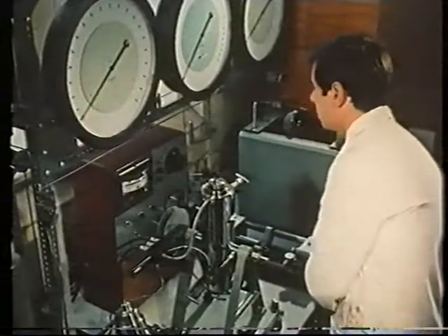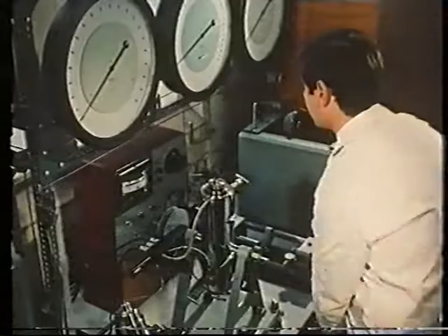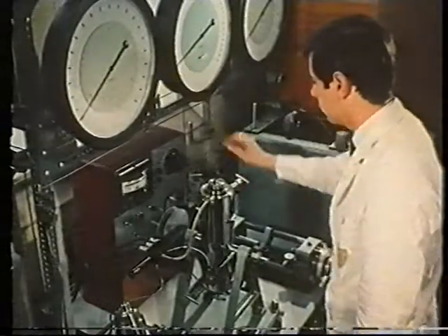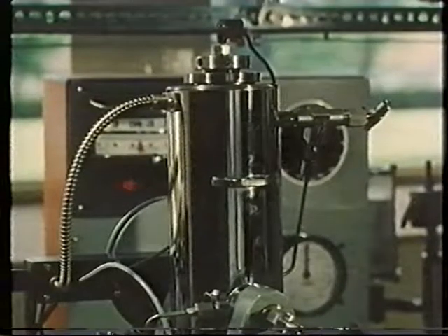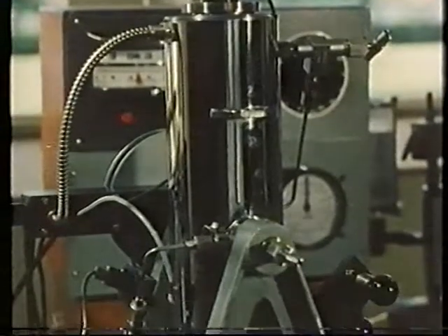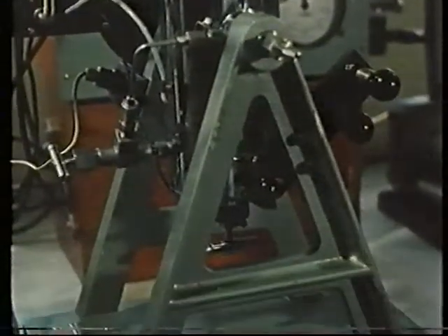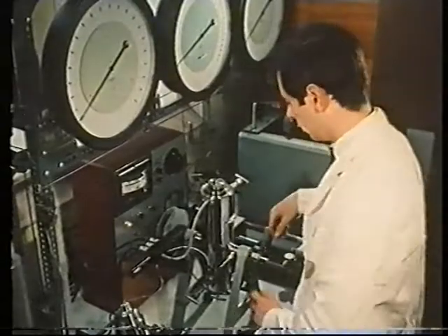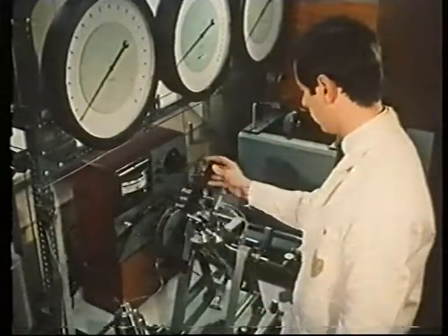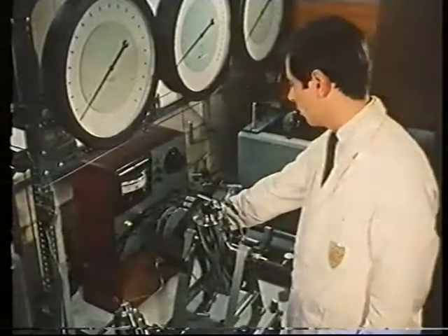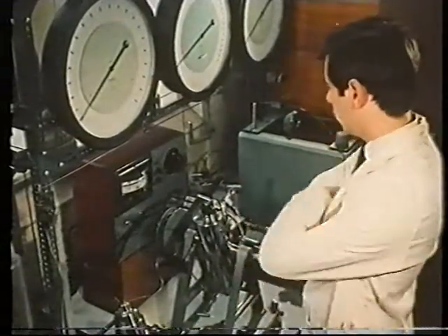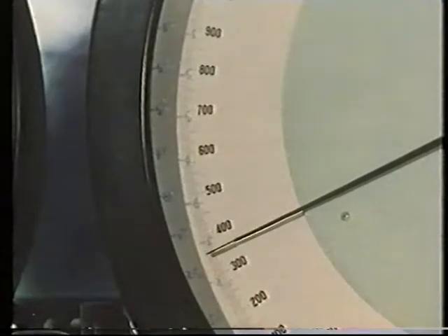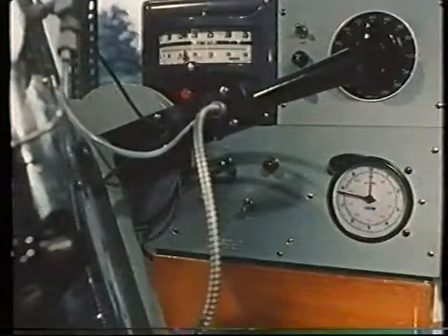System design must also take into account the effect of pressure on certain properties of hydraulic oils. This pressure viscometer measures change in viscosity with change in pressure. At the top of the cylinder is a ball. When the ball is released, it starts a timer, which stops when the ball reaches the bottom. At a pressure of 350 atmospheres, the ball falls in eight seconds.